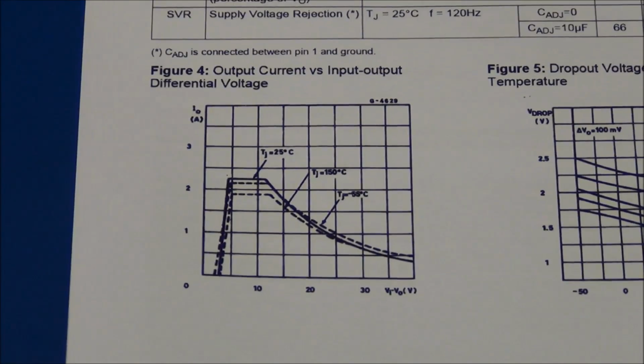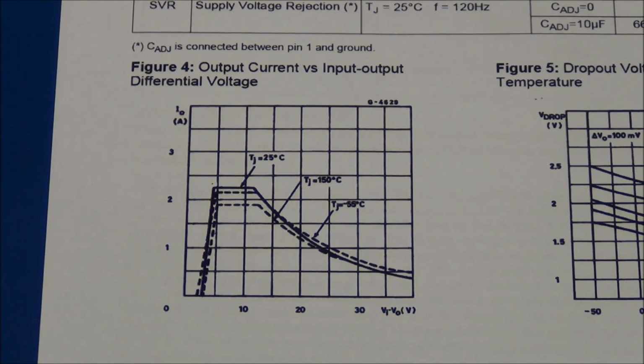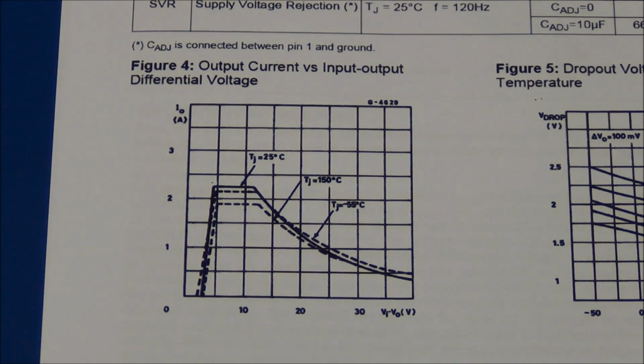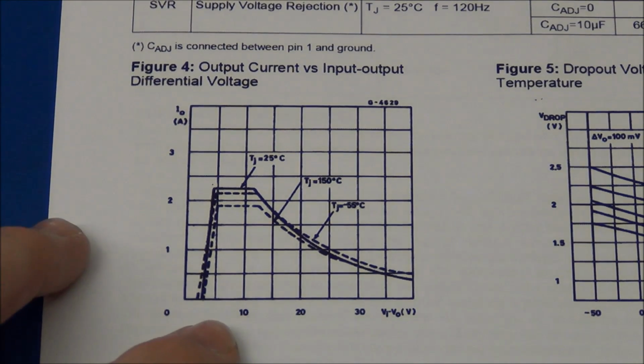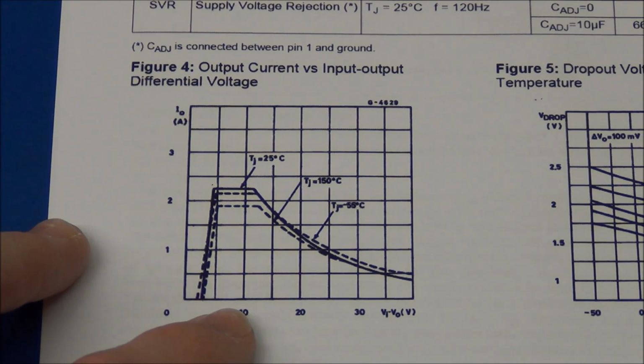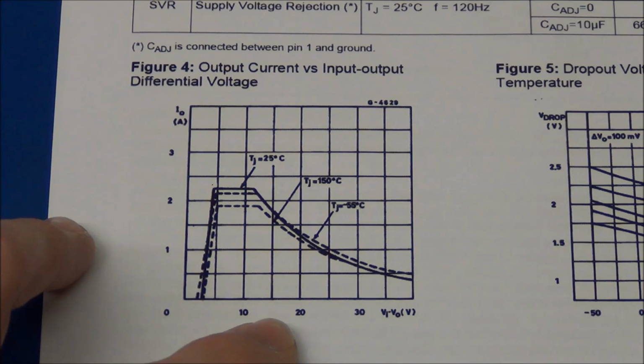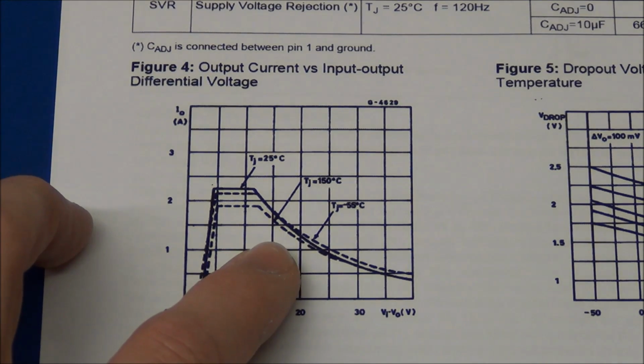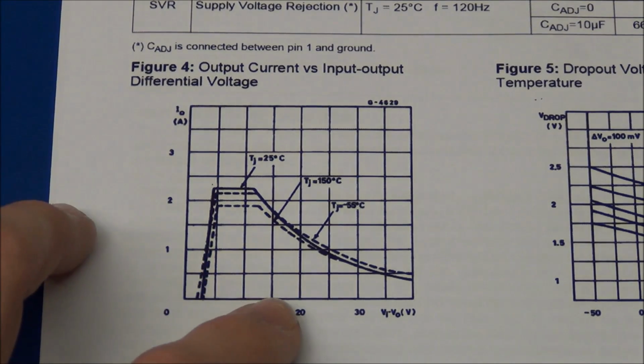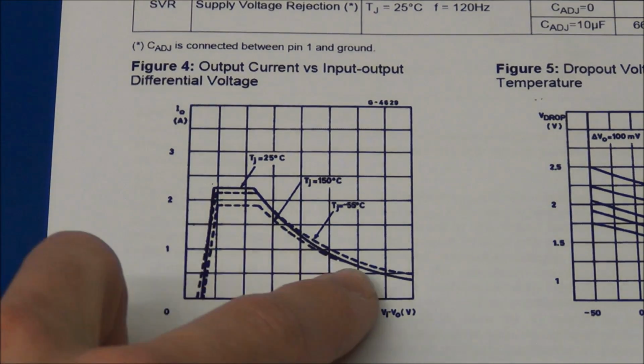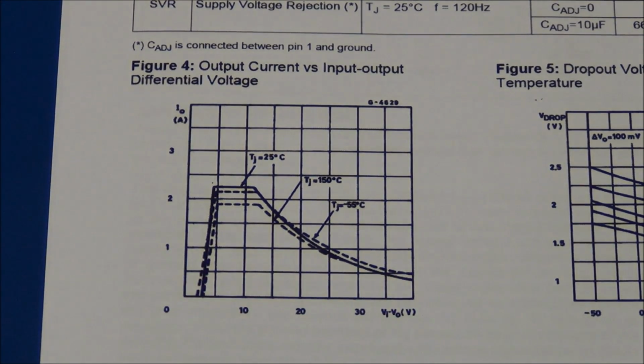And if we take a look at this graph I talked about earlier, about output current versus input-output differential voltage, you can see that we can only have an input-output differential voltage of about 15-17 volts if we want the full 1.5 amp output. If we go above that, the output current will drop off.